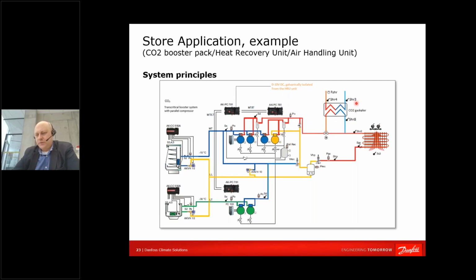Another topic: when we are speaking about a secondary heat exchanger, which is not drawn here, you have to build a double heating system for the air handling unit. I mean, 1 heat exchanger from the cooling rack will accommodate it, plus a heat exchanger, plus probably hundreds of meters of pipes to the air handling unit. The air handling unit will be larger. It will have 2 heat exchangers, because one will be from heat recovery, another one from the district heating utility. So the customer is buying 2 systems.